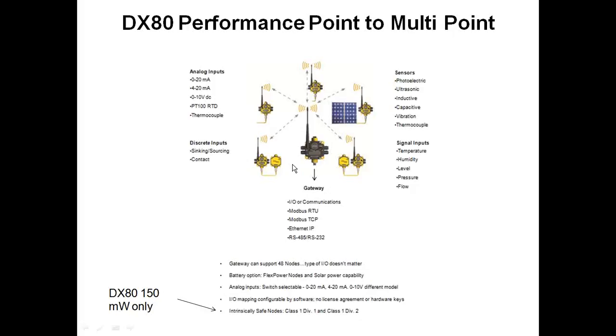With this family, now we can start doing a lot of the flex power or battery things with small modules or solar panels. The other big advantage is you now pick up the capability to pull Modbus RTU out of the gateway, which is our resident serial package. If you want to do Modbus TCP or Ethernet IP, it's just a different gateway, we call it Gateway Pro, but it looks identical.